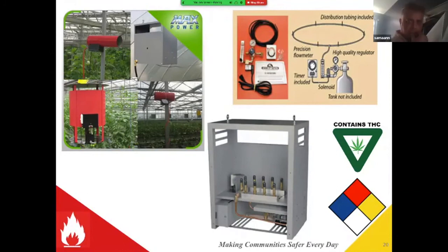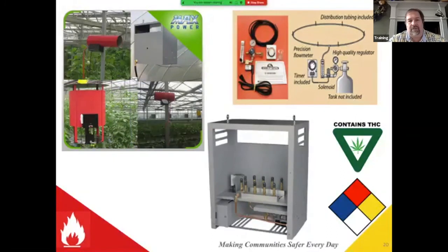the majority will change anyways, because they're unlisted equipment typically. And then when they find out the additional BTU load that's required for both the moisture and the latent and the sensible heat, they rethink it, and then they wind up going to a bottle or a bulk tank system.